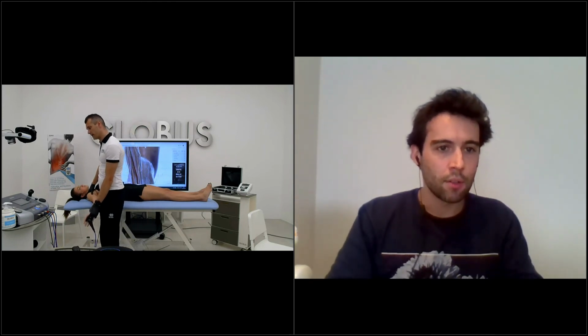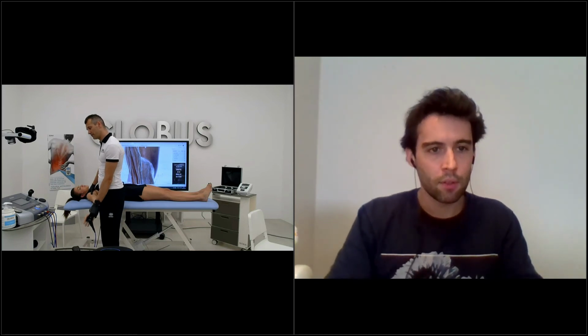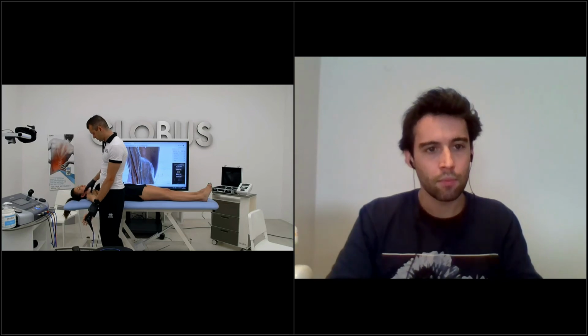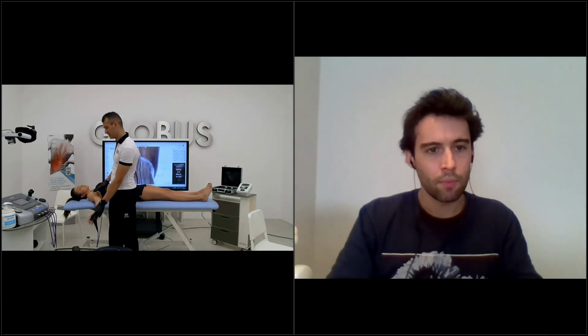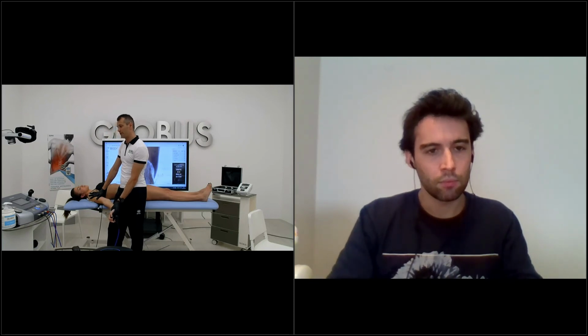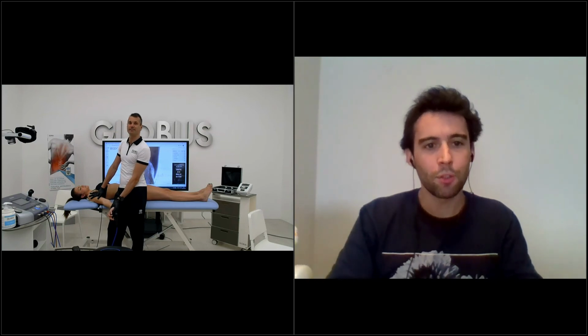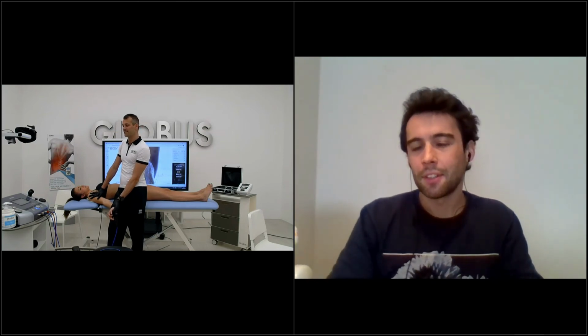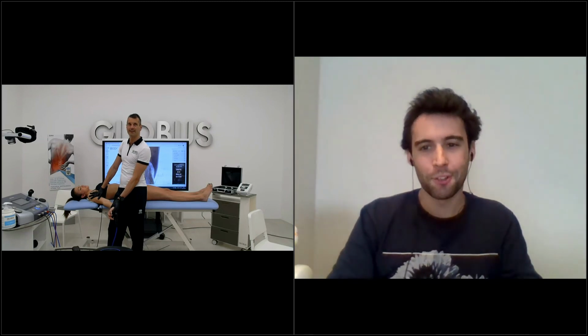All right, so here we are working with 58 to 60 watts. So we are promoting the energy through the whole upper limb, as you can see. Do you feel any warm sensation? Yes. Where? Okay, she's perceiving some warming inside the hand. Is it correct? Okay. It's good.